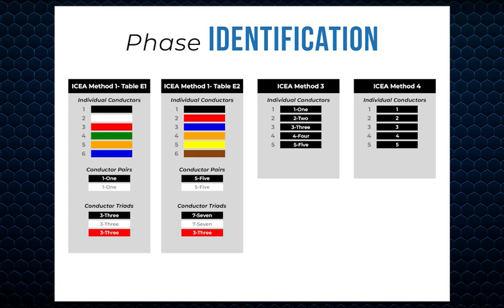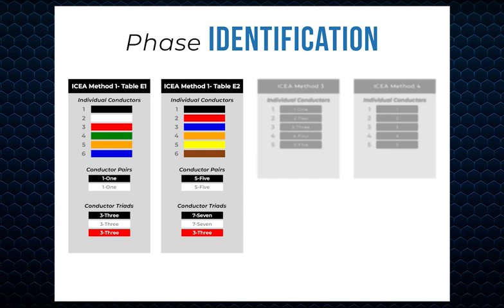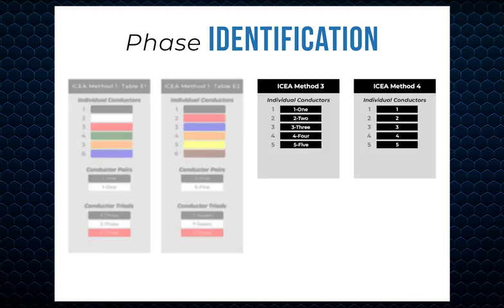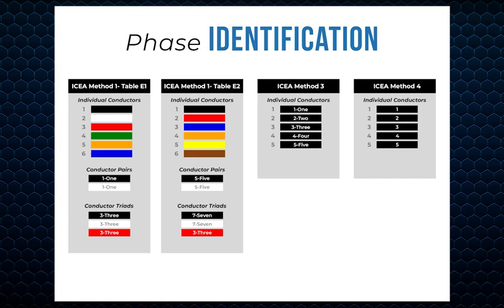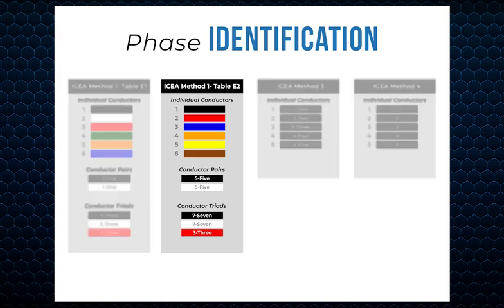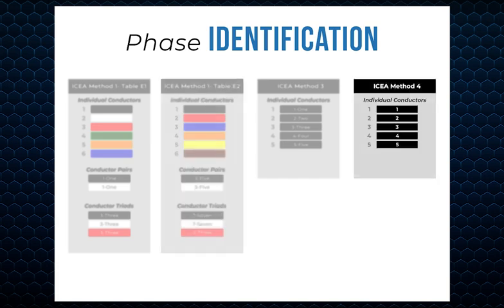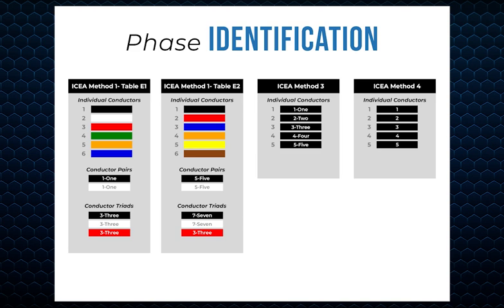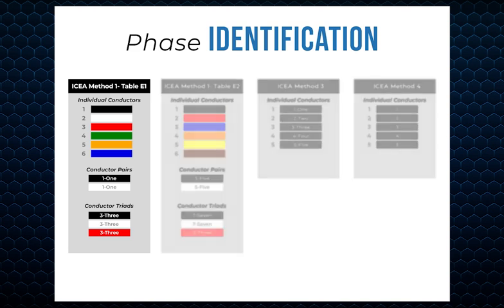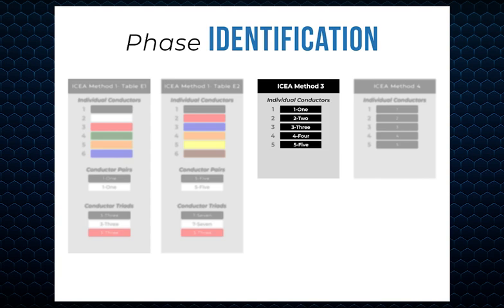Cable insulation is also used for conductor identification. Color coding allows you to quickly identify, test, and terminate multi-conductor cables. ICEA Method 1, tables E1 and E2, utilize color to identify individual conductors, while ICEA Methods 3 and 4 use black insulation with printed numbering. Most industrial end users specify ICEA Method 1, table E2 for 14 gauge through 10 gauge, and ICEA Method 4 for 8 gauge through 1000 kcmil conductors. Utilities, on the other hand, specify ICEA Method 1, Table E1 for 14 gauge through 10 gauge conductors, and ICEA Method 3 for 8 gauge through 1000 kcmil.